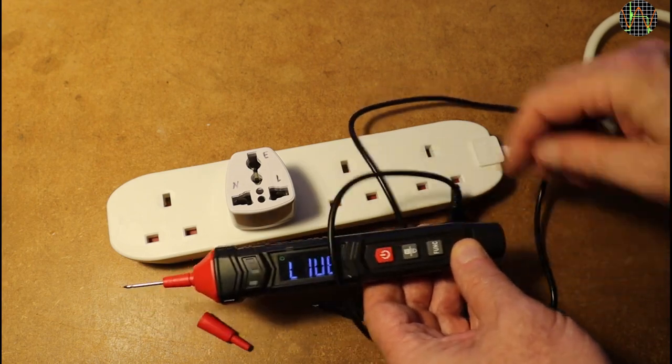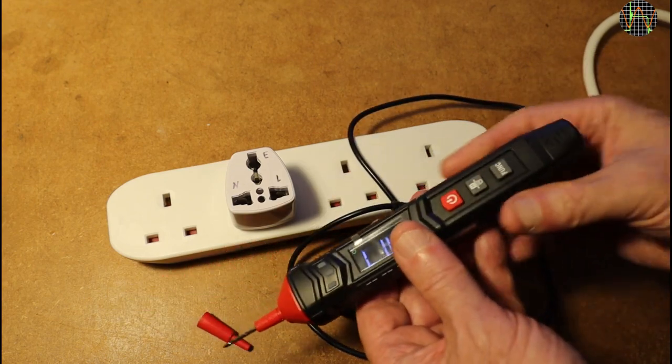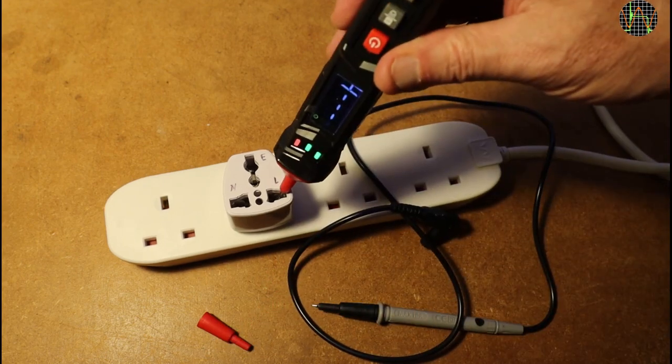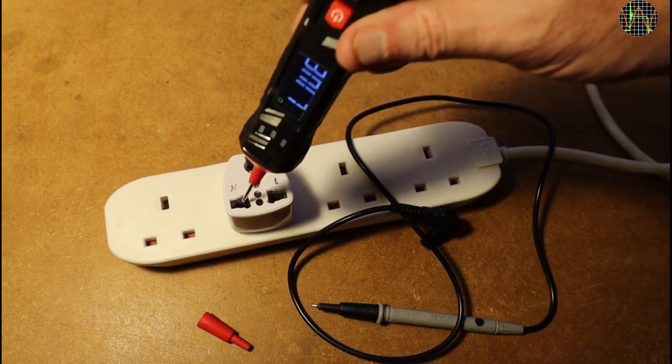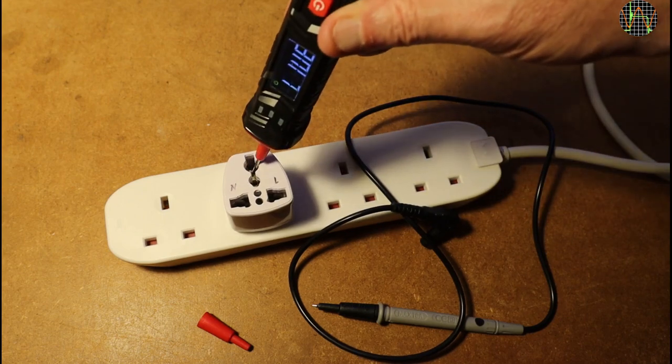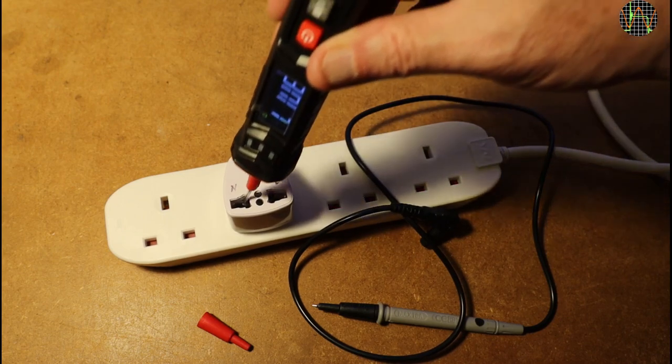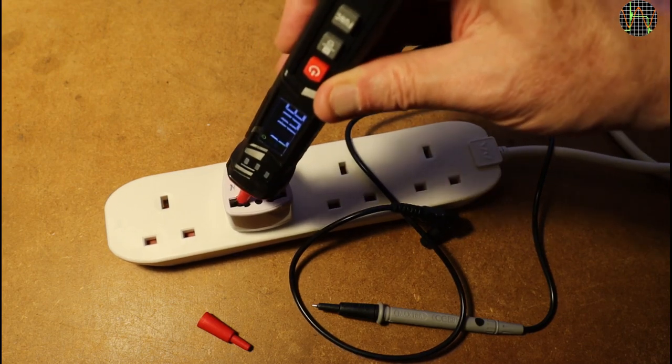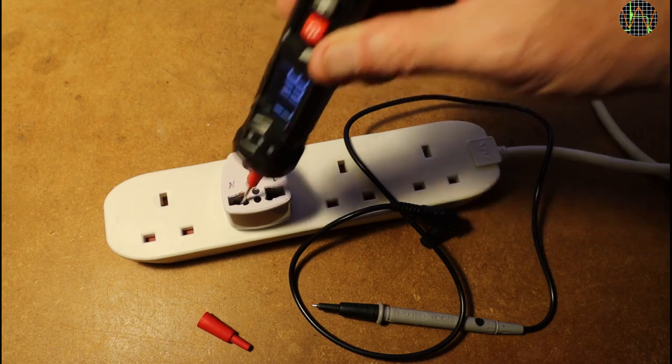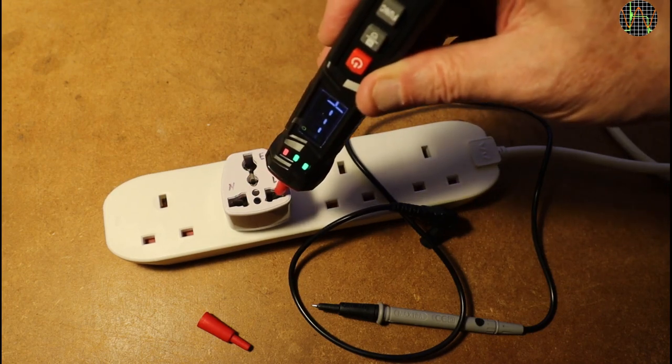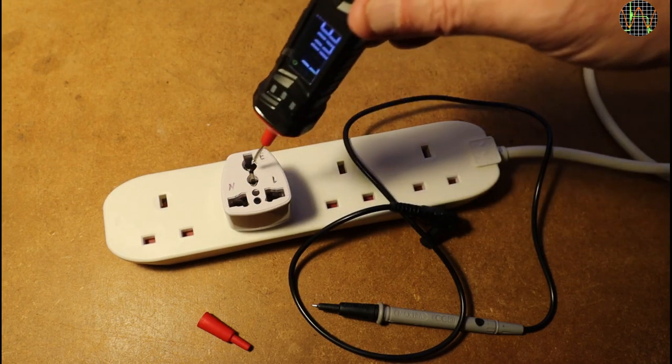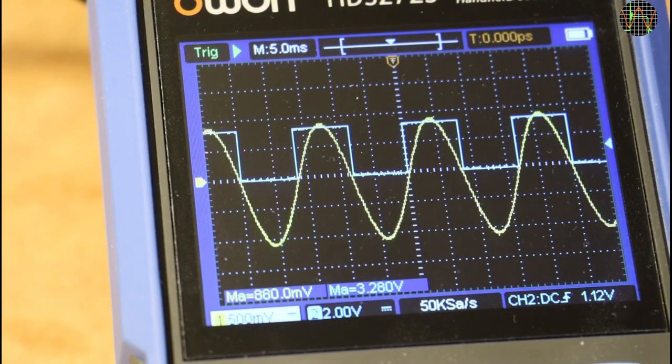I have to criticize the manual here because while it says that the red probe is used for this test, it does not explicitly say to remove the black lead. Repeating the test with the black lead removed, it behaves properly and detects the live phase and only the live phase as it should.